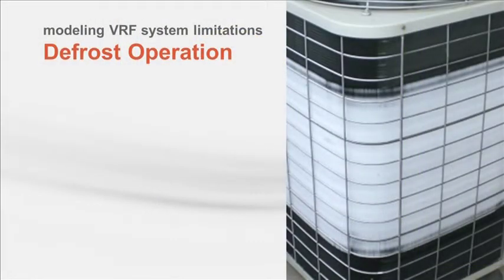Defrost operation allows the outdoor unit to remove any frost and ice buildup on the outdoor coil when operating in the heating mode. Remember that the heat exchanger in the outdoor unit serves as an evaporator when the system is predominantly heating, and this usually occurs when it's cold outside. If a single outdoor unit is used, the system will operate in cooling mode for several minutes, so hot refrigerant is routed to the outdoor unit to melt any built-up ice or frost. Of course, when this occurs, the indoor unit discharges cool air into the space regardless of demand.